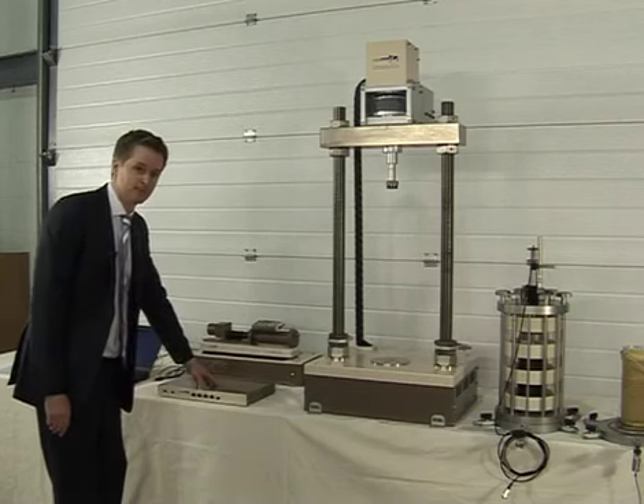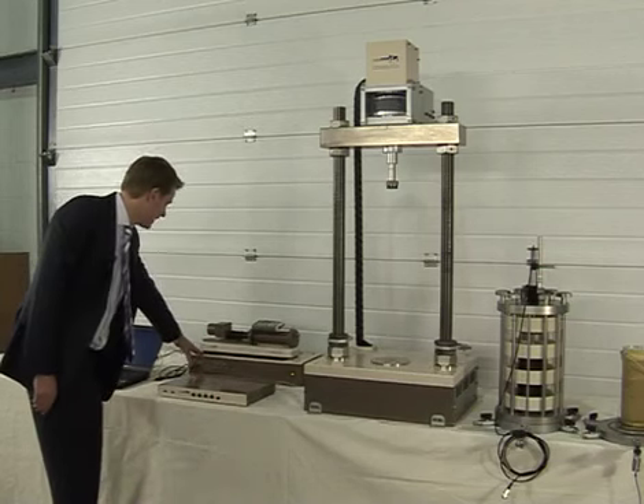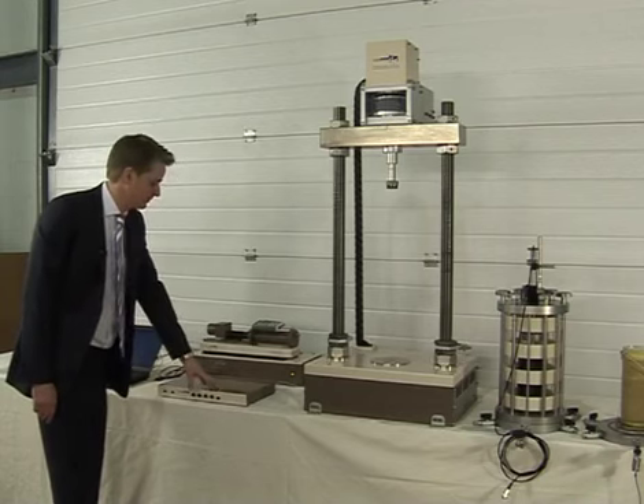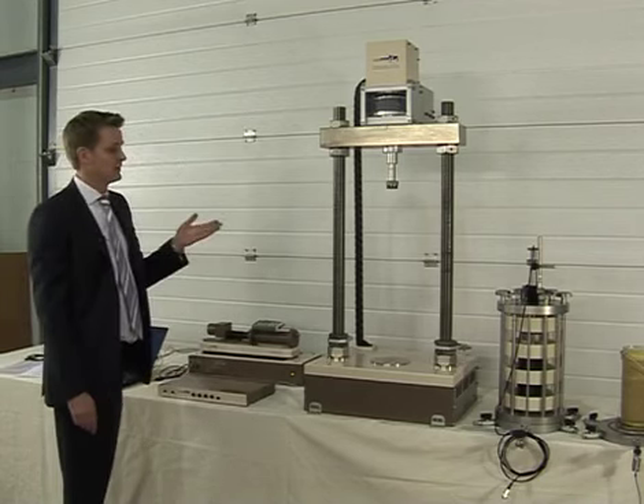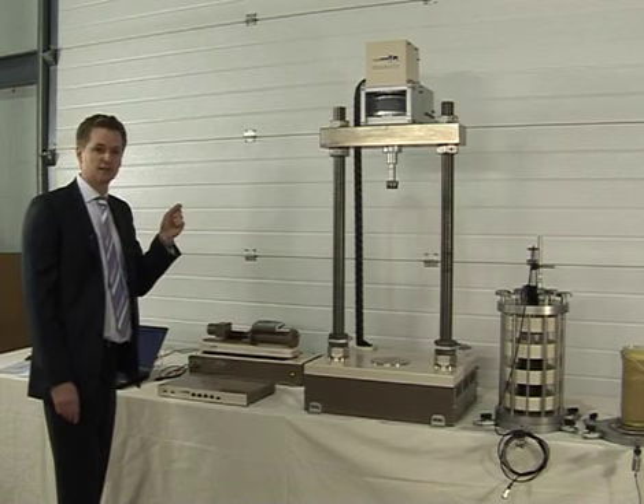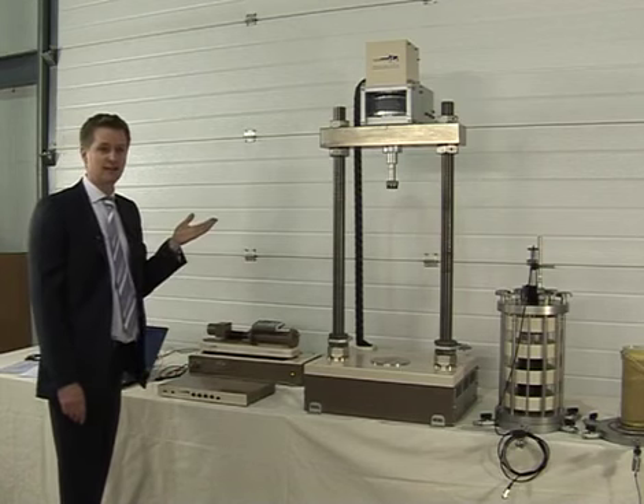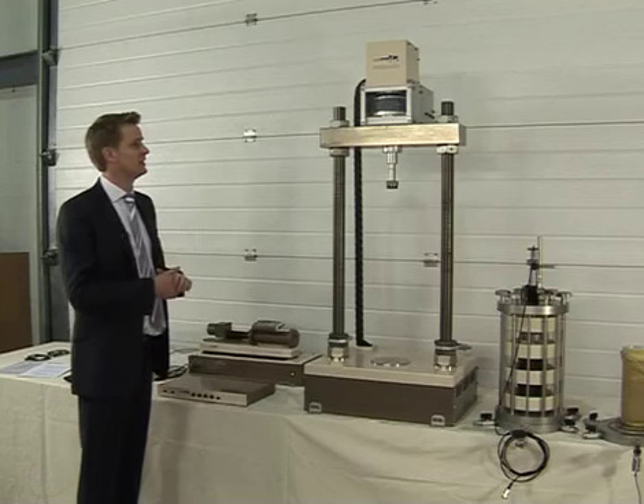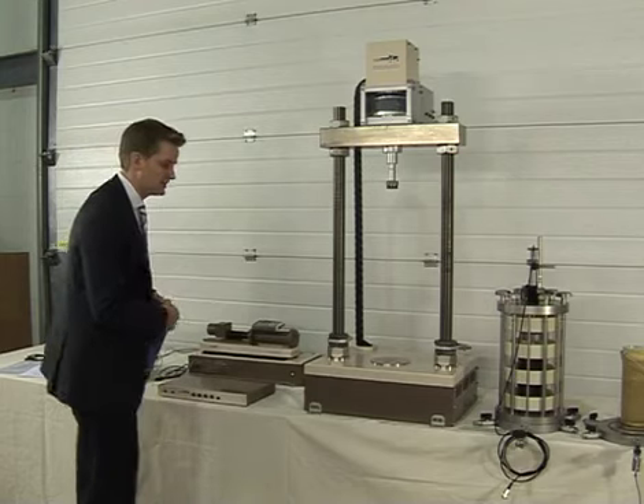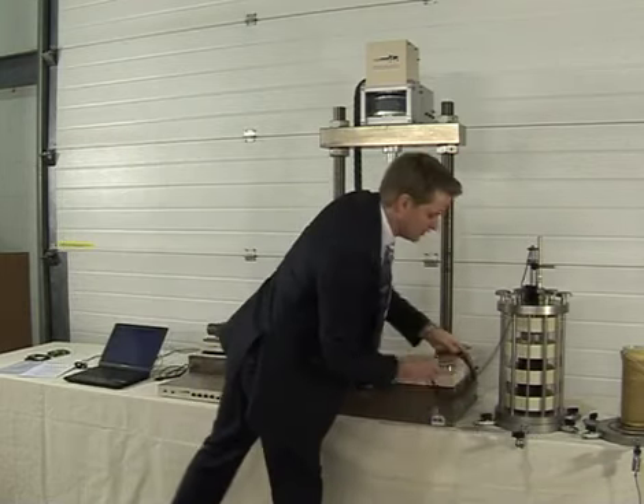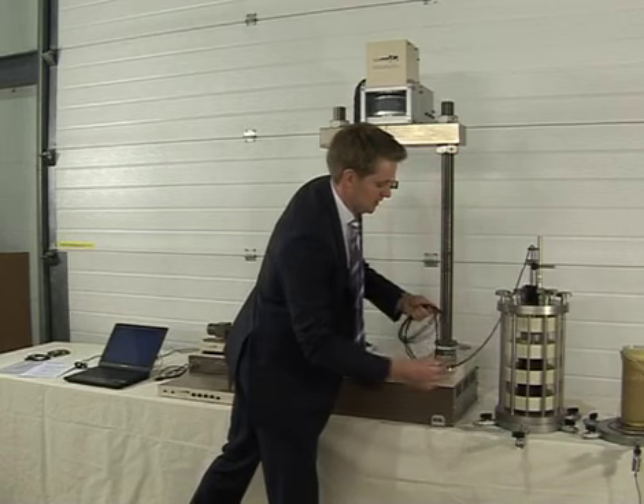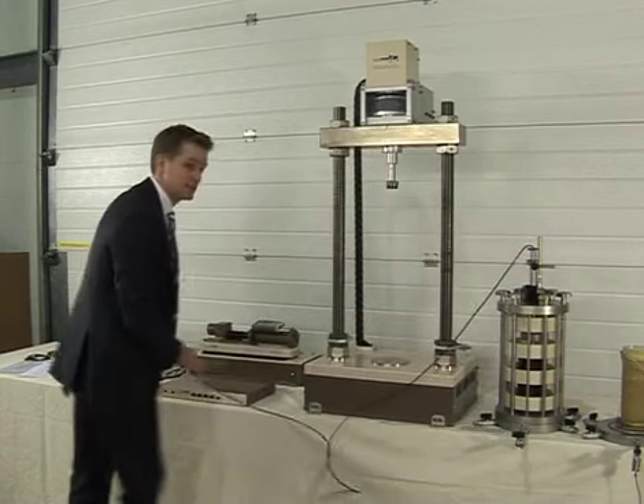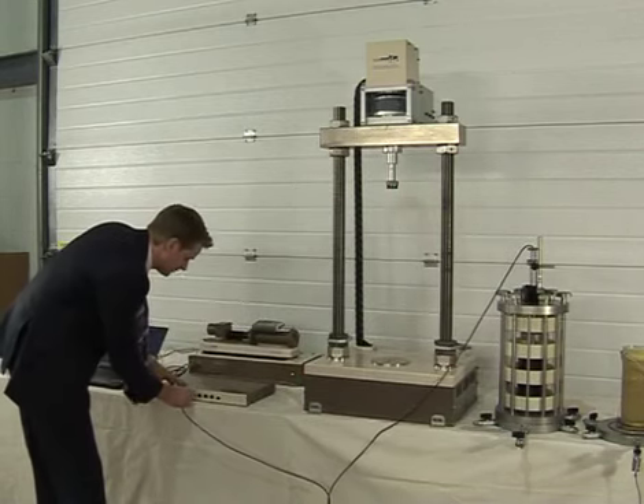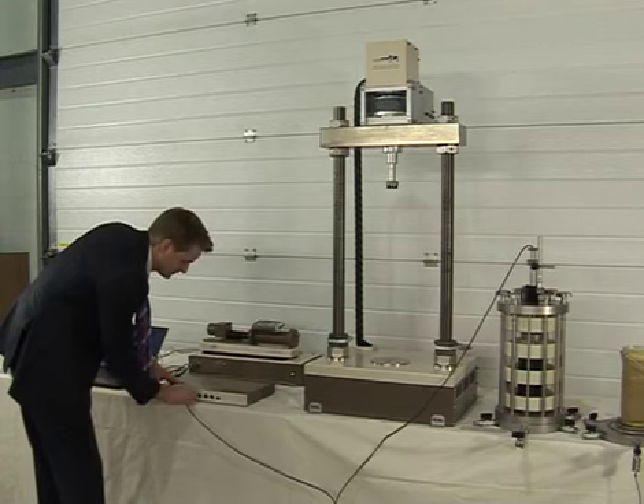In this system, I'm going to be using the output of the cell pressure controller because we don't have a displacement transducer. Not entirely necessary because we're going to measure the displacement using the high accuracy encoder built into the actuator. So let's connect the load cell to channel 0 with its plus or minus 30 millivolt input range.